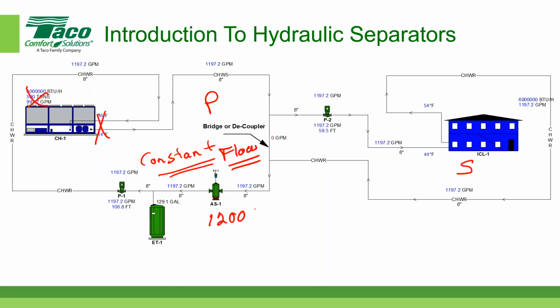So the secondary circuit, usually the secondary circuit is made up of a bunch of terminal devices that have two-way valves. What do I mean by that? I've shown a building here, but the piping inside that building, I could have a supply, for example, and let's say the supply has flow from left to right. And at some point, I take a branch off of that supply and maybe go through an air handling unit, let's say an air handling unit coil, and then a two-way control valve. And then I'd be connected to the return line, okay?